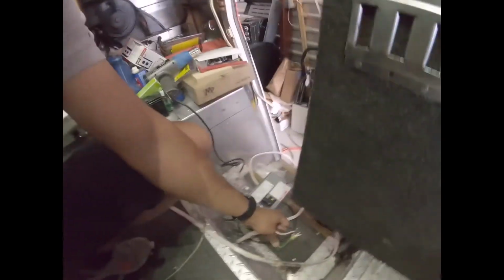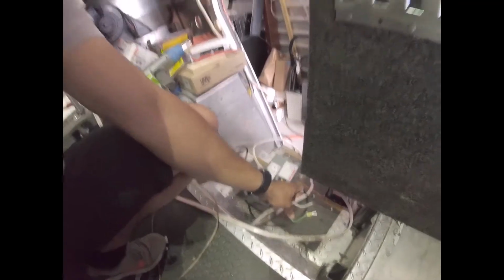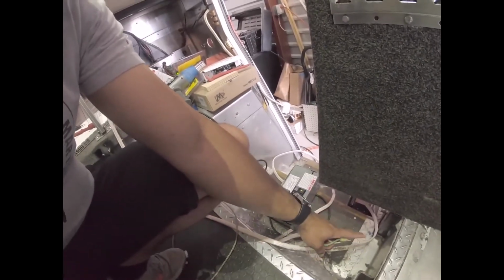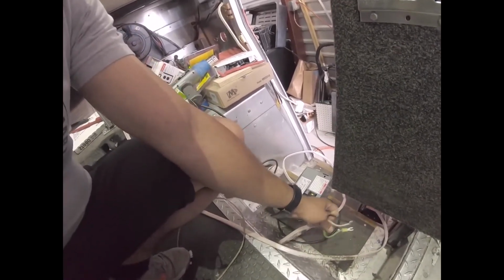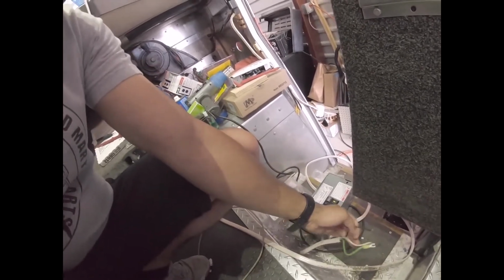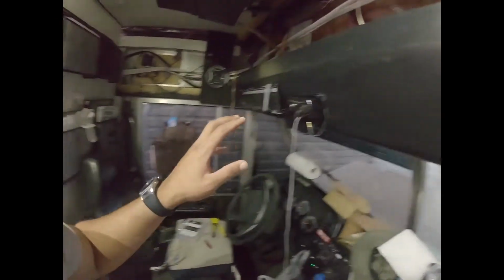That might be why, safety first. Okay, so these are the outlets I disconnected. They're grounding out to the chassis here because these are still open. This is your ground, this is your power, and this is your neutral. And that's still running up to here. So you just experienced what a short circuit, and a breaker that's actually working doing its job, is. Let me get those wires covered up and we can try that again.